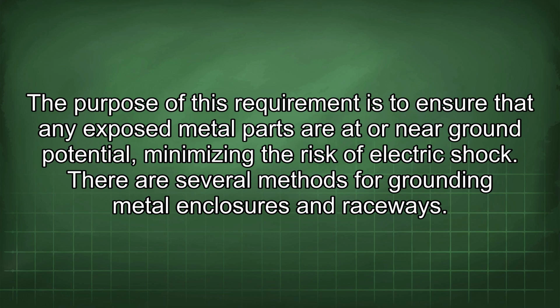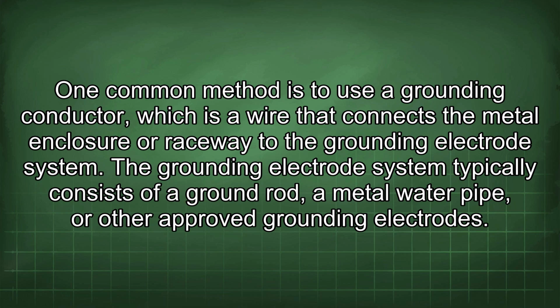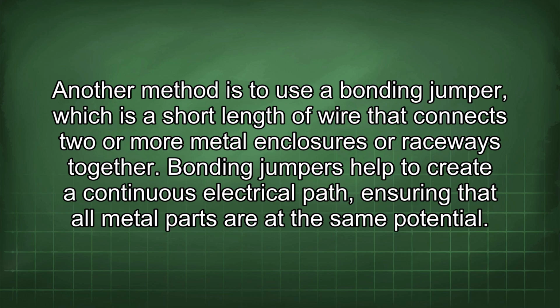There are several methods for grounding metal enclosures and raceways. One common method is to use a grounding conductor, which is a wire that connects the metal enclosure or raceway to the grounding electrode system. The grounding electrode system typically consists of a ground rod, a metal water pipe, or other approved grounding electrodes. Another method is to use a bonding jumper, which is a short length of wire that connects two or more metal enclosures or raceways together. Bonding jumpers help to create a continuous electrical path, ensuring that all metal parts are at the same potential.